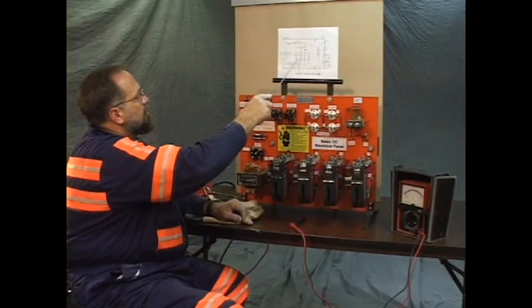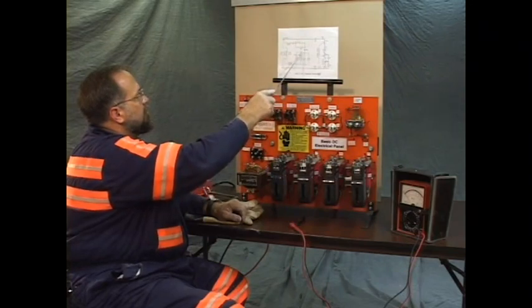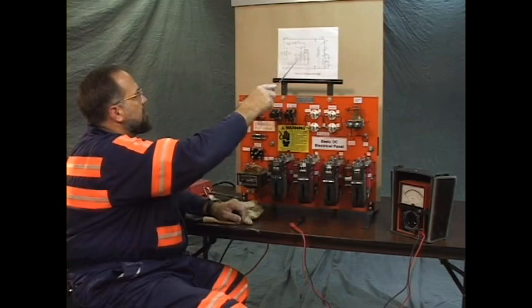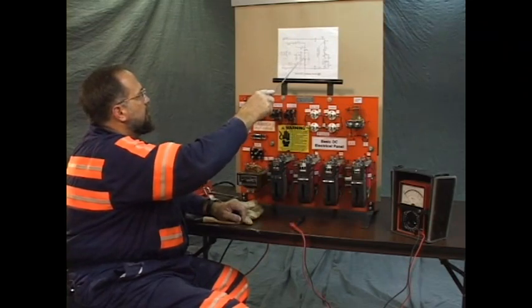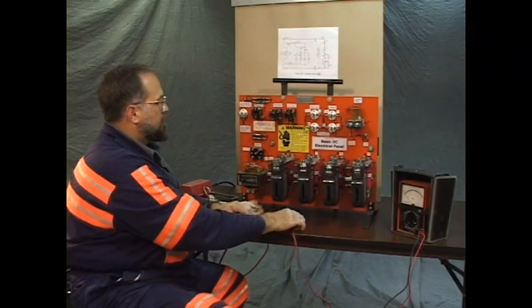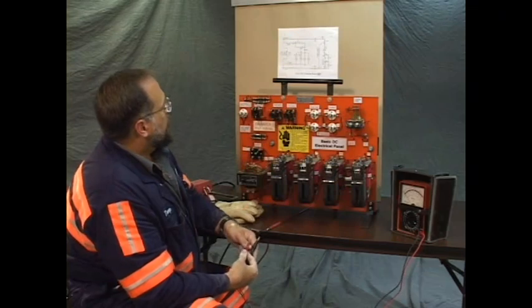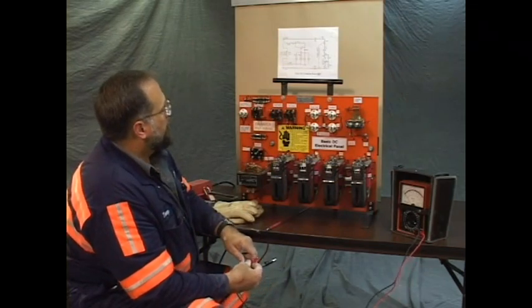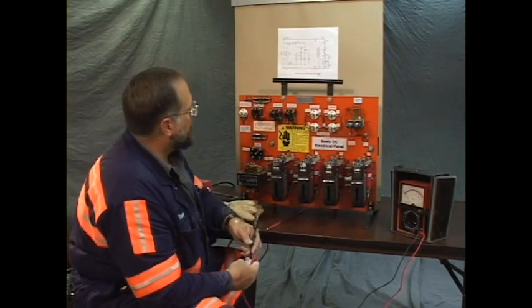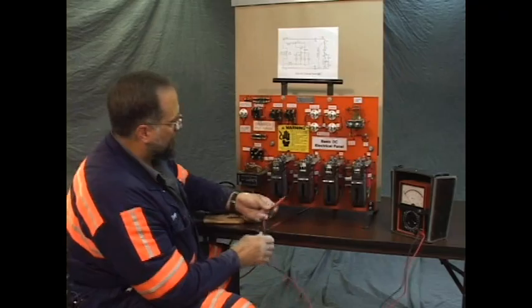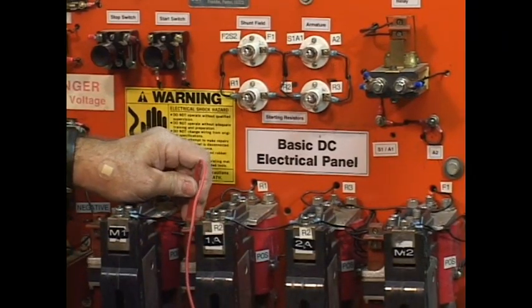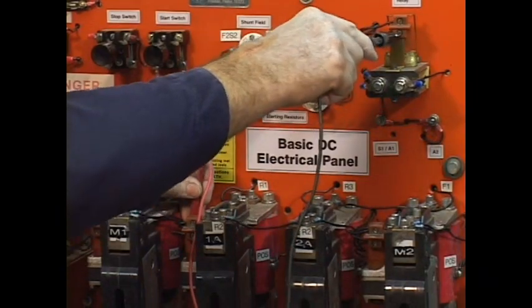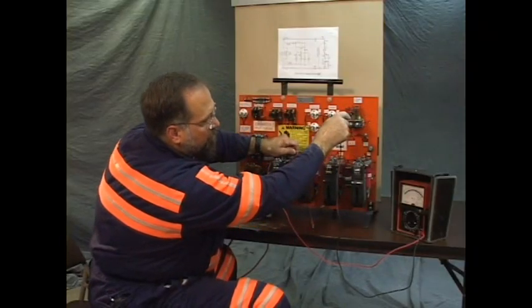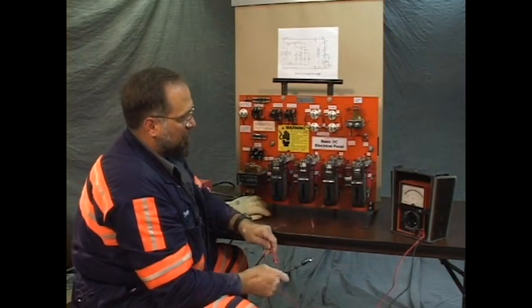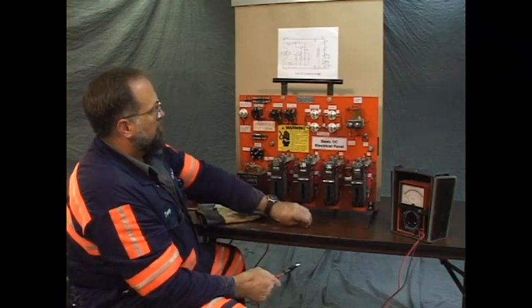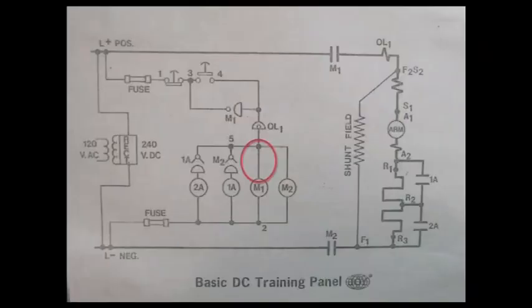By the closing of these contactors, 2A, 1A, and M2, we can be reasonably certain that all this is intact. Now, the problem lies between here and here. Let's check that. We'll begin at the load side of the OL1 mercury tube and check to the positive of the M1 contactor, and check to the positive of the M1 contactor coil. And we have it. So that part of the circuit's good. From here to here is good.